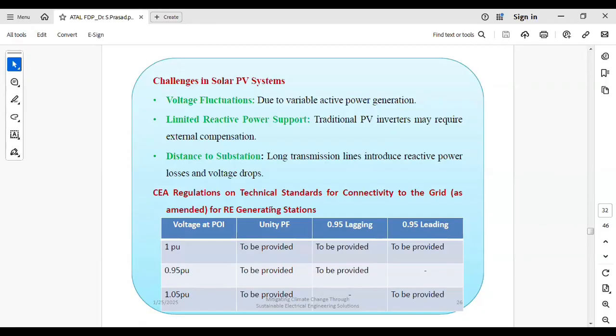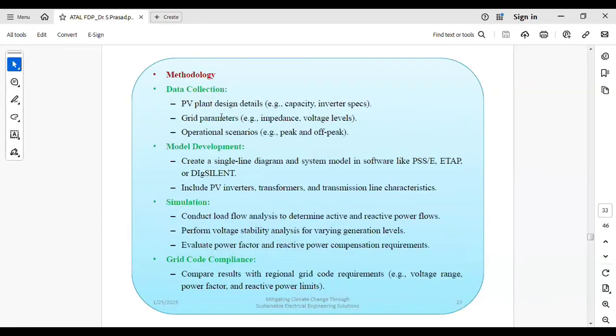Okay, so that analysis we need to perform to finalize the size of the capacitor bank or reactive power compensating device at the PV end, so that because of the PV plant, the grid should not get disturbed. The PV plant should not absorb reactive power from the grid. Otherwise, you will get a voltage imbalance at the grid end. Okay, so therefore a reactive power analysis study is performed. This is also one of the important tasks.